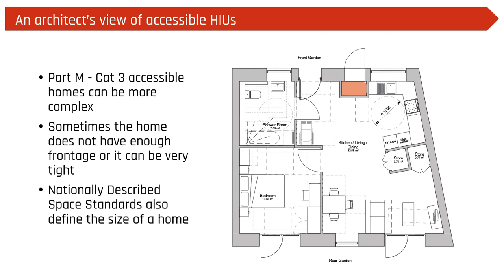We're also, a lot of our schemes are dual aspect, so we need a thermal line on both sides of the building, so we need to insulate the wall. We're finding the easiest way to do this is to include the HIU inside the dwelling and keep the external wall line on the outside, so that we're not costing more in building that cupboard. So the only cost difference is the door, and a little bit of an internal wall, but that would happen anyway inside a dwelling. So in order to keep costs down, we keep the thermal line on the outside.